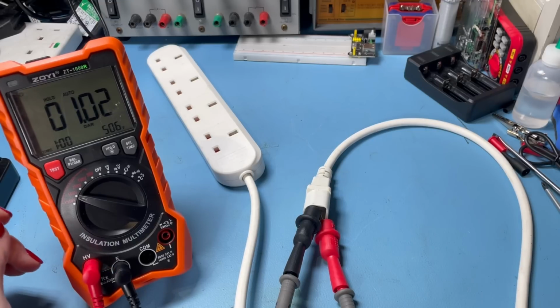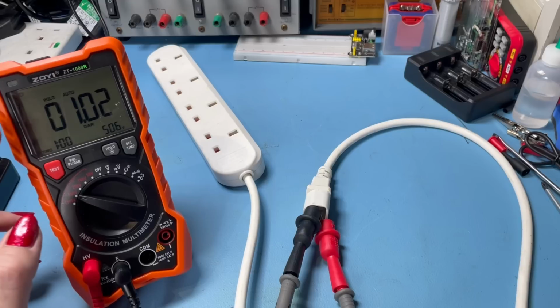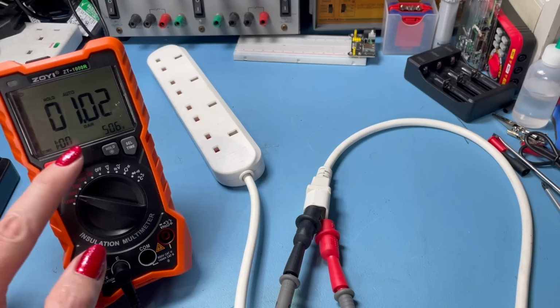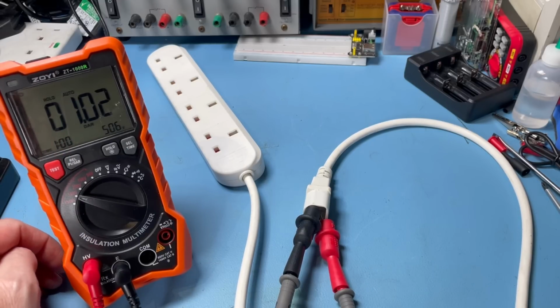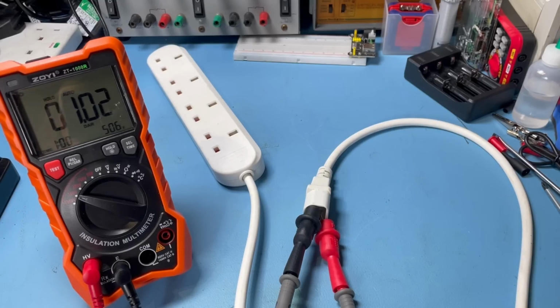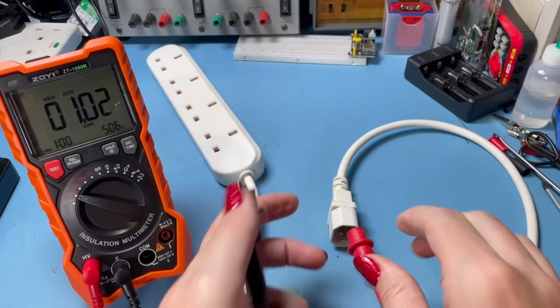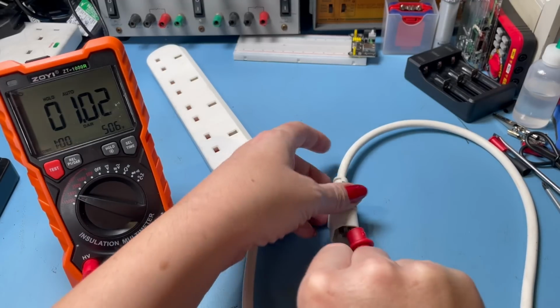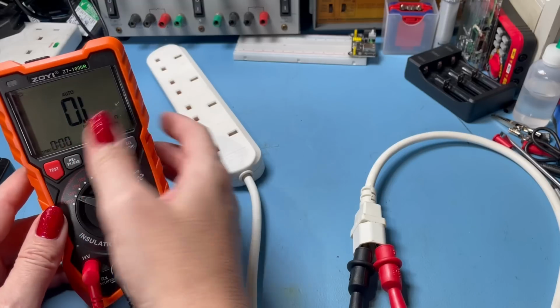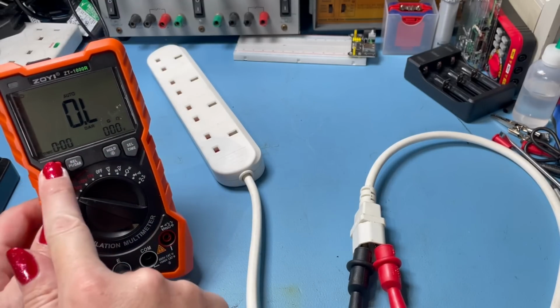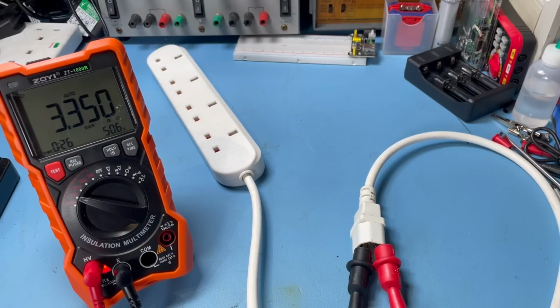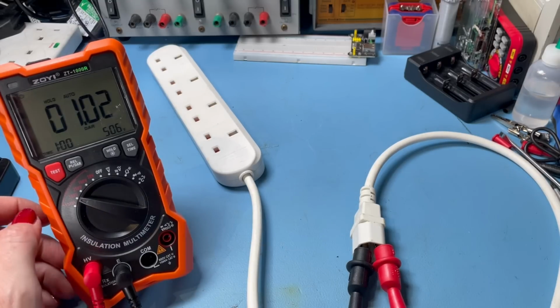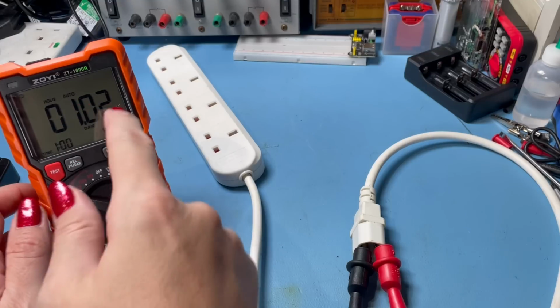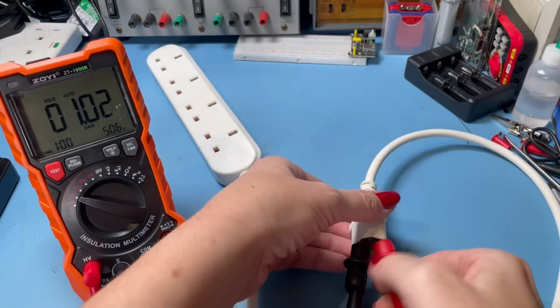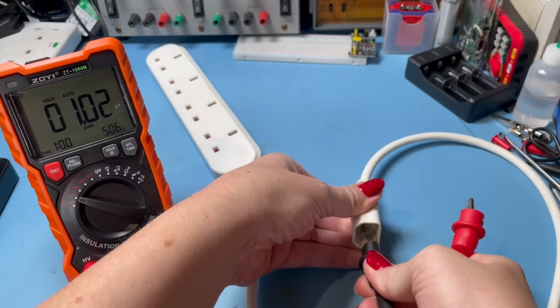Okay, so you can see your insulation resistance was climbing there. We got up to nearly 3.5 gigohms, and it's given me a DAR of 1.02, which is very acceptable for an extension lead like this. Okay, so I'm now going to go neutral to earth and repeat the test. Same again, DAR, neutral to earth. Not quite as high resistance on that one, not a lot in it. We finished with a DAR of 1.02, which is not a million miles away from where we were before.